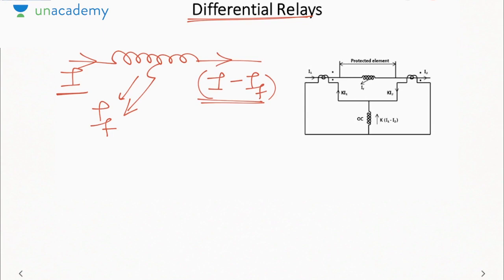So that is how we can use a differential relay. It basically checks the difference between the currents at the two ends of the coil, and it passes that difference into an overcurrent relay, which will check if the difference of the two currents is greater than the pickup value. Basically, what does an overcurrent relay do? It checks if the operating current is greater than the pickup current. Here the operating current will actually be the difference of the current at the two ends of the line.